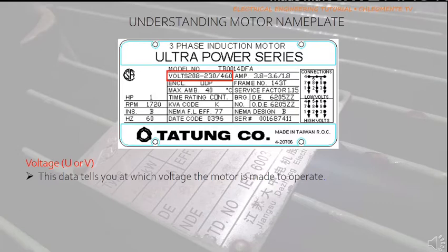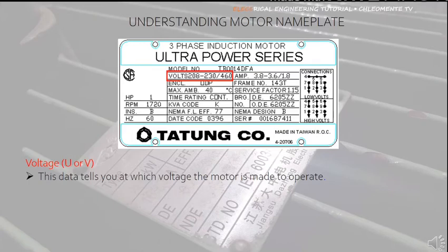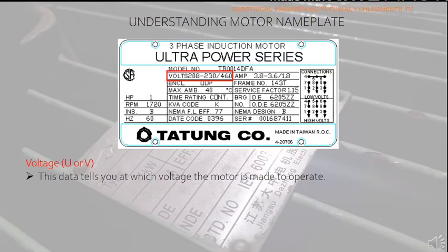The first parameter we will discuss is voltage, normally denoted by letter U or V. This data tells you at which voltage the motor is made to operate. The motor's power factor, efficiency, torque, and current are at rated voltage and frequency. When the motor is used at voltages other than indicated on the nameplate, its performance will be affected. In this example, the rated voltages are 208 to 230 volts and 460 volts, meaning this motor can be operated at low or high voltage depending on the leads connection.